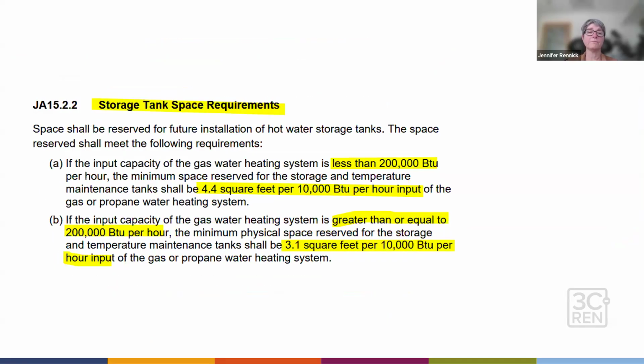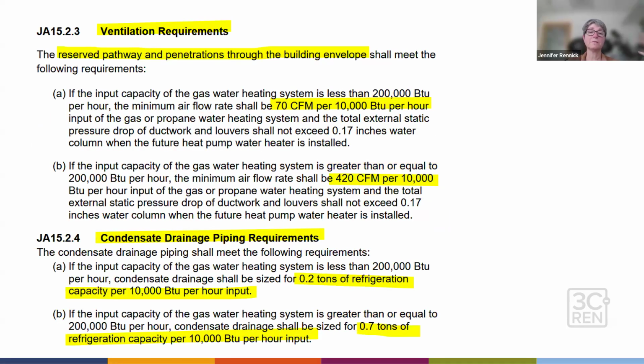if they've chosen to install a gas boiler central heating system. And there's similar requirements for the storage tank space in the sense that, again, based on whether it's less than the 200 kBTU or greater than the 200 kBTU per hour, that would determine how many square feet per 10,000 BTU of capacity you would have reserved for the tanks. And then ventilation requirements follow a similar pattern. If it's more than or less than the 200 kBTU, it's going to be determined based on 10,000 BTU per hour of installed gas unit capacity, with a multiplier of 70 CFM for the smaller requirements or 420 CFM per 10,000 BTU for the larger requirements.